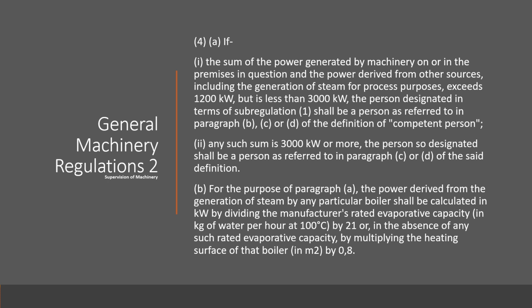For the purpose of paragraph A, the power derived from the generation of steam by any particular boiler shall be calculated in kilowatts by dividing the manufacturer's rated evaporative capacity in kilograms of water per hour at 100 degrees Celsius by 21, or, in the absence of any such rated evaporative capacity, by multiplying the heating surface of that boiler in square meters by 0.8.